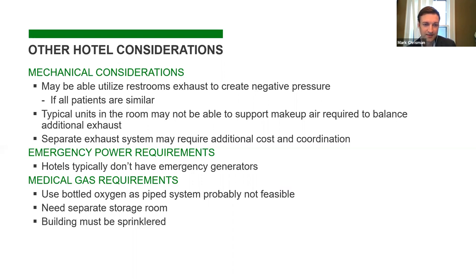The medical gas, in terms of being stored, requires us to create a separate room with its own ventilation requirements for exhaust and supply. And one other critical thing was that since these patients aren't going anywhere, it was very important that these buildings were safe—sprinklered with a fire sprinkler system, and with a fire alarm system with smoke detectors for early detection.